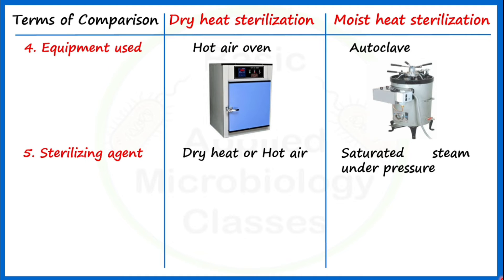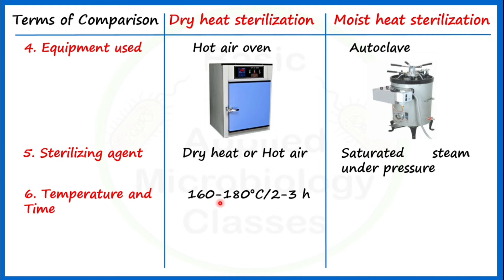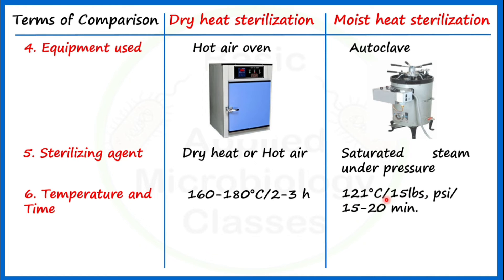The sixth point of difference is the temperature-time combination. Generally, 160 to 180 degrees Celsius is used in dry heat sterilization for two to three hours. In the case of the autoclave, we use 121 degrees Celsius at 15 PSI pressure for 15 to 20 minutes. This is the most commonly used time and temperature combination.